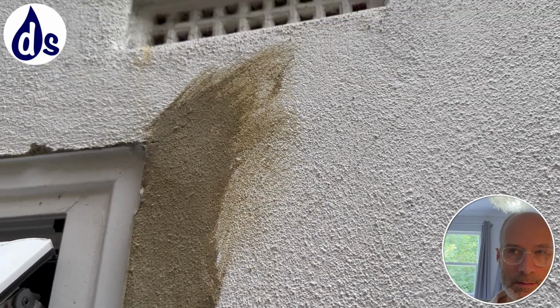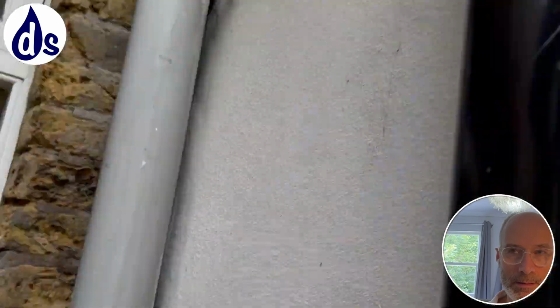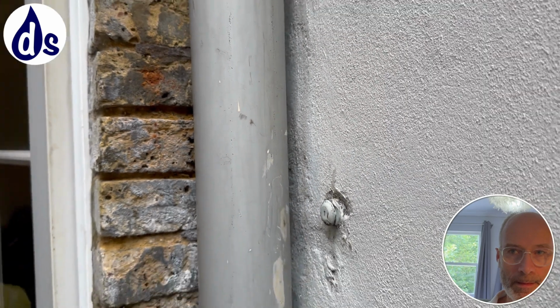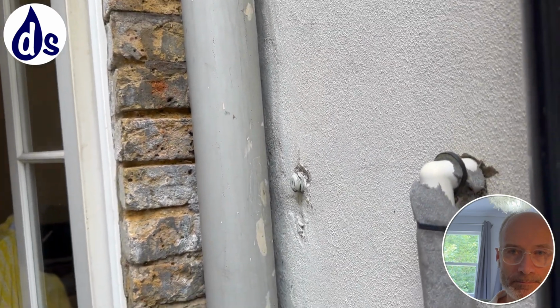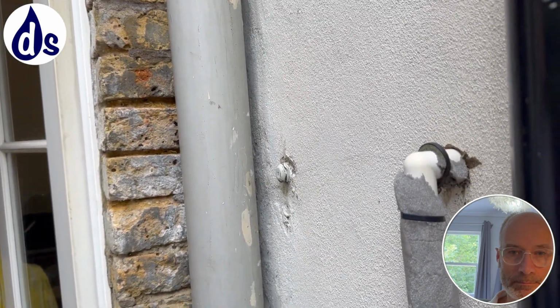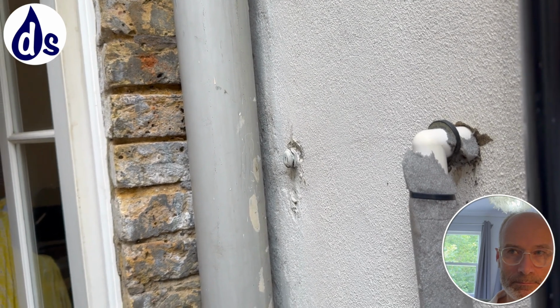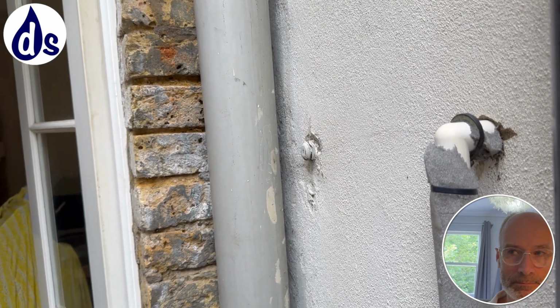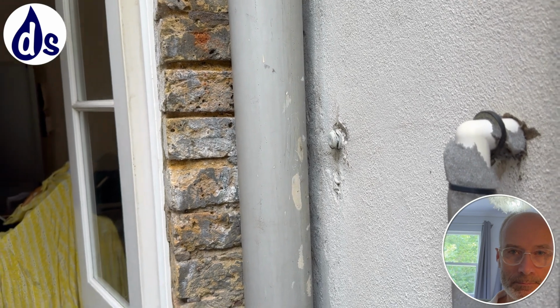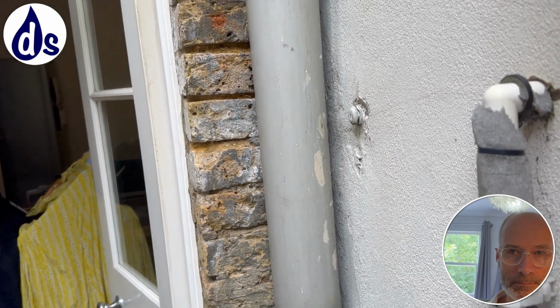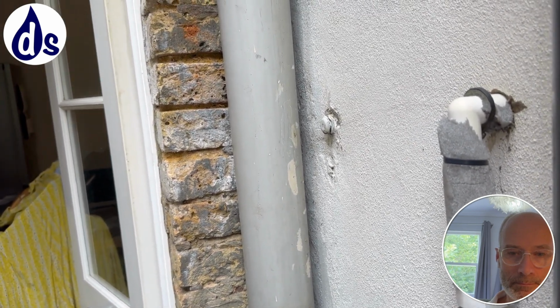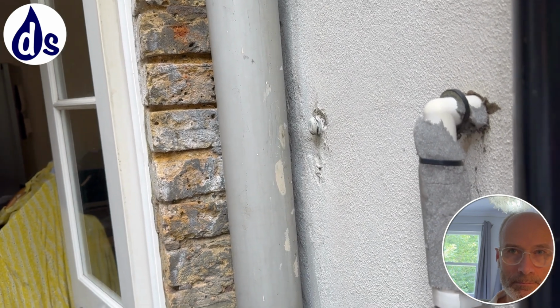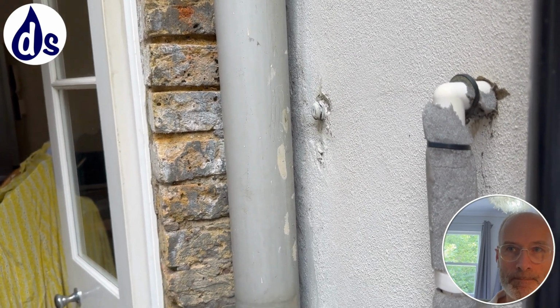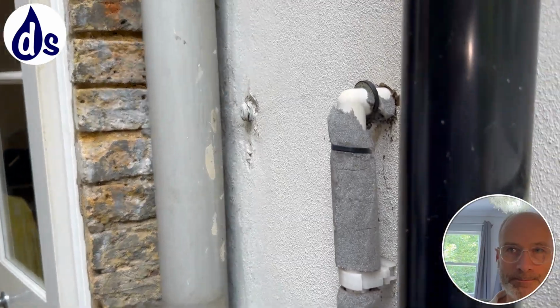Ideally you get a little bit of rigid pipe, like this is rigid pipe, because you get less resistance through that. But if they have to use a plastic flexible ducting, just make sure it's absolutely taut, so it's pulled as much as possible. Otherwise you get this effect of huge resistance from the pipe itself.